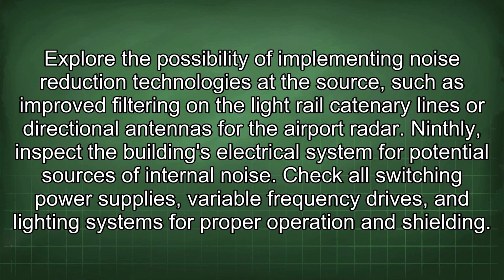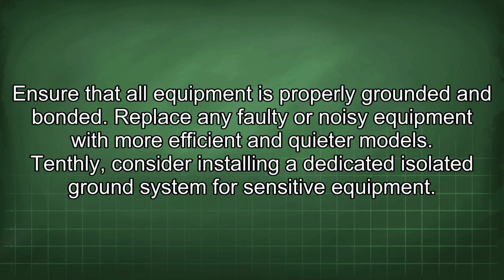Ninthly, inspect the building's electrical system for potential sources of internal noise. Check all switching power supplies, variable frequency drives, and lighting systems for proper operation and shielding. Ensure that all equipment is properly grounded and bonded. Replace any faulty or noisy equipment with more efficient and quieter models.